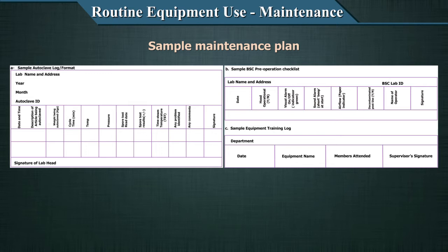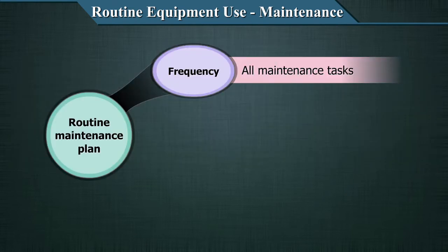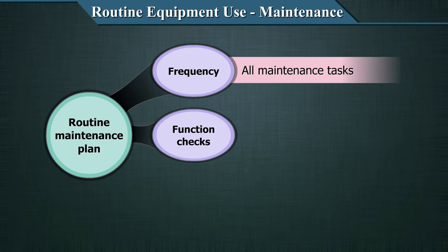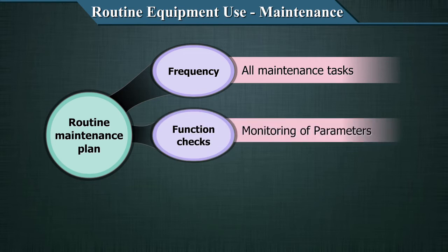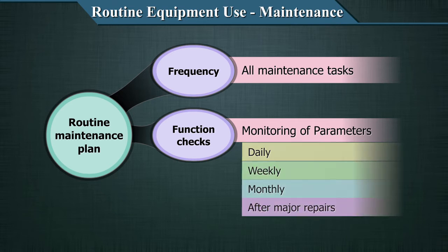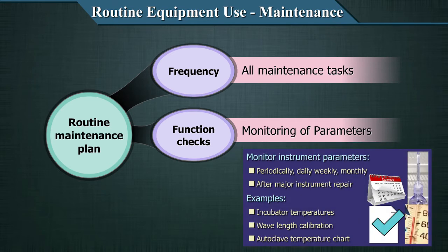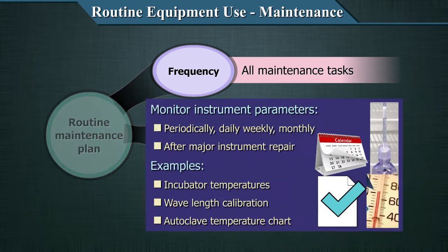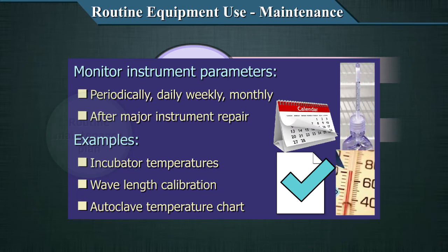The maintenance plan should also include function checks, which involve monitoring of instrument parameters periodically — daily, weekly, and monthly. Some examples of function checks include incubation temperature, wavelength calibration, autoclave temperature chart, and others. These should be monitored and documented as required.